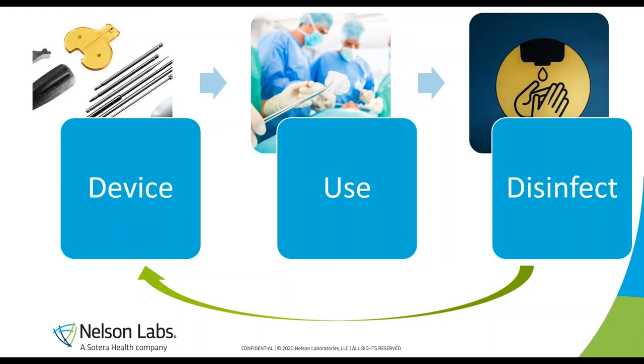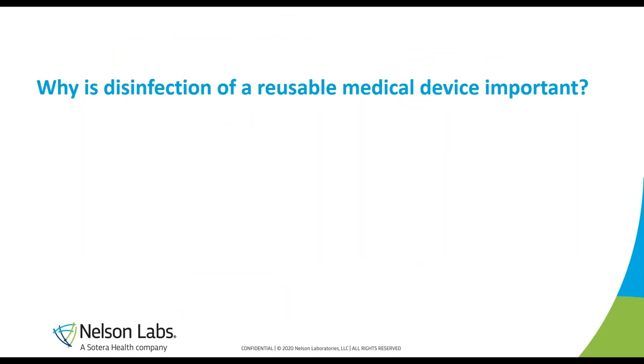We all know how to disinfect our hands, but how do you disinfect a device in order to reuse it? Disinfection of a reusable medical device is important because if the device is contaminated with microorganisms, you want to ensure that for the next patient there are no microorganisms present, or the risk is significantly reduced — and also to protect healthcare workers from cross-contamination. It's very important that microorganisms on the device are killed.